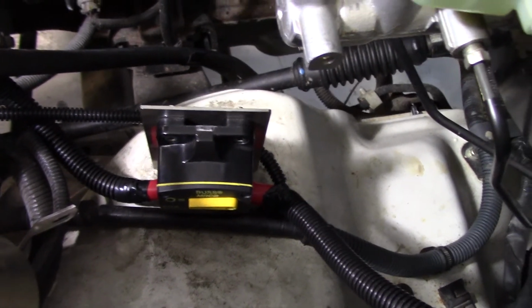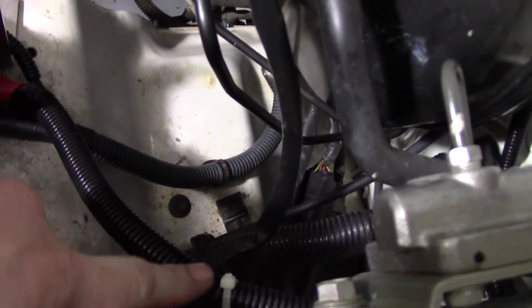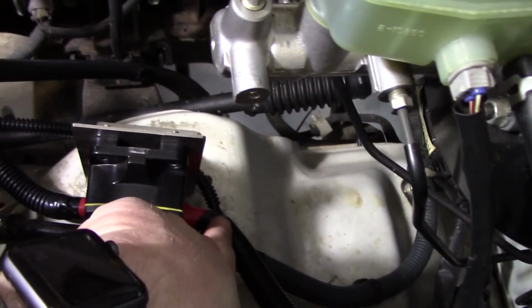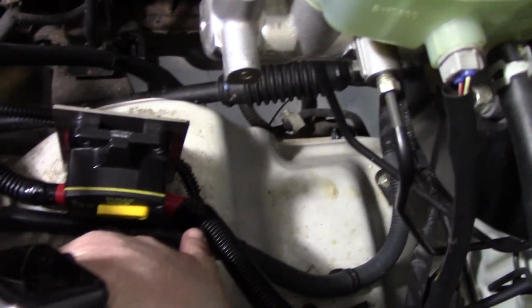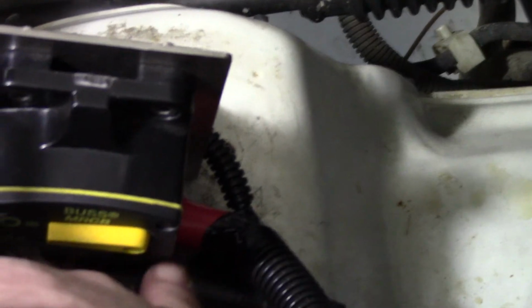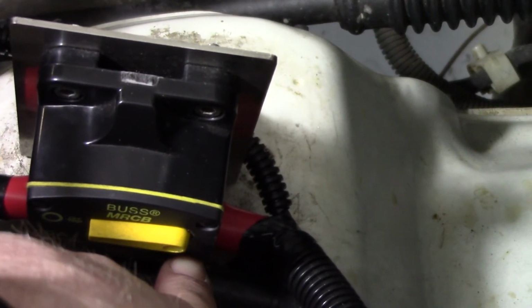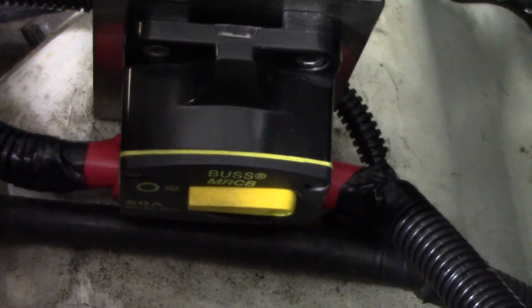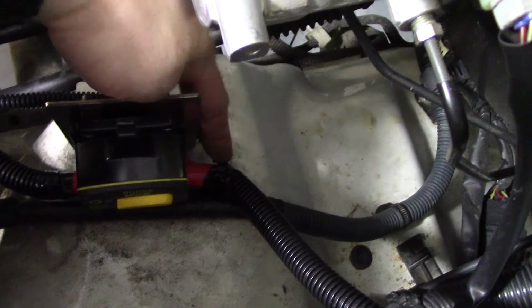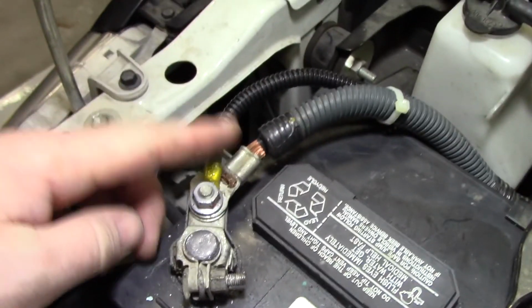Okay, so here's the finished product. We've got our power cable, black and red wires coming in, and the black wire splits off and goes behind the circuit breaker. The red wire comes into the load terminal on the circuit breaker, and then we cut our red line and hooked it back up on the line side of the circuit breaker. The line side I ran up to the positive terminal of the battery, and then back to the circuit breaker. The negative line comes back behind here, goes alongside the battery, and hooks into the negative terminal.